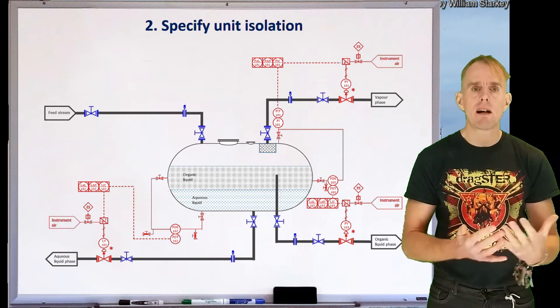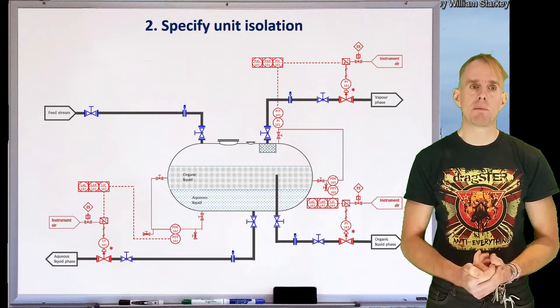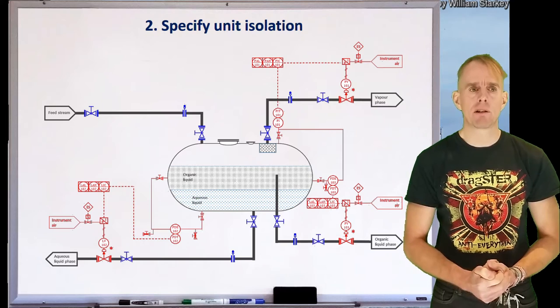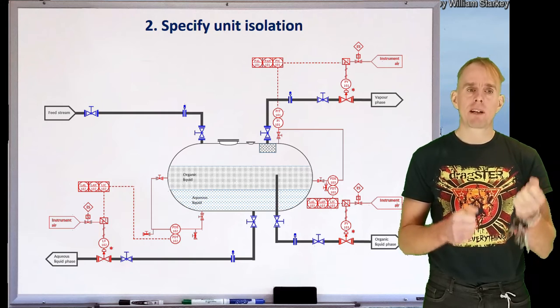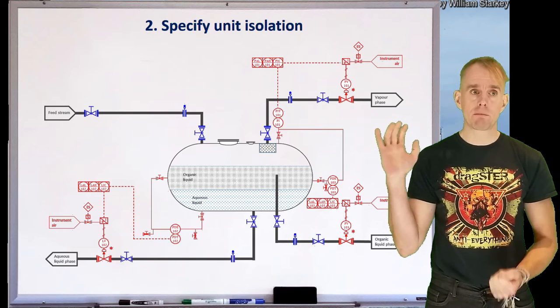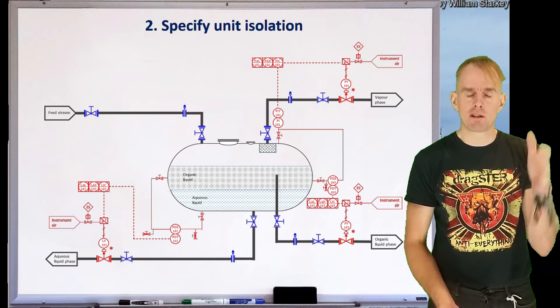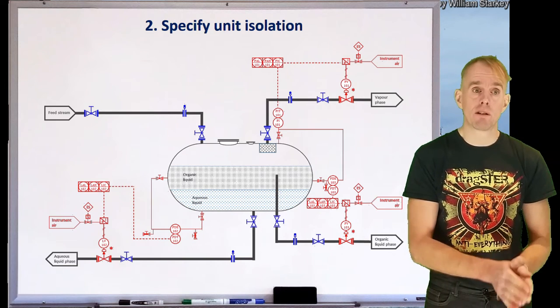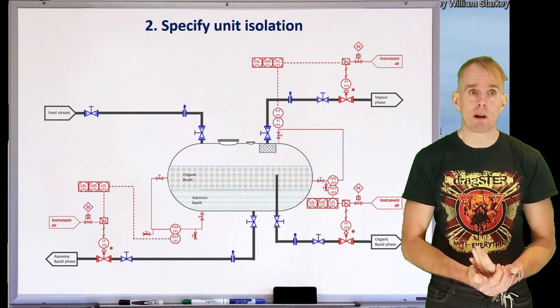We want to be able to safely isolate this unit in times of shutdown. There could be cause for people to enter the unit to inspect it, and we want to rely on more than just a single closed valve. The standard is double block and bleed: double block means shutting off connections to and from the vessel in two different ways. I've illustrated normally open valves and also spectacle plates — solid pieces of material inserted into a pipe flange and bolted shut, providing a solid barrier. Double block and bleed is the standard for isolation.